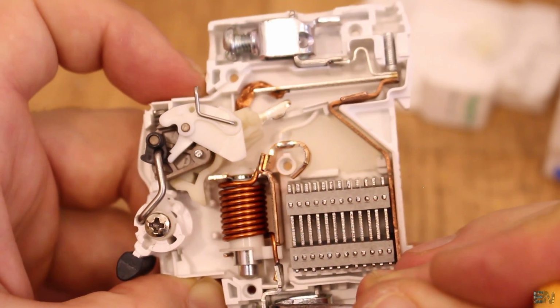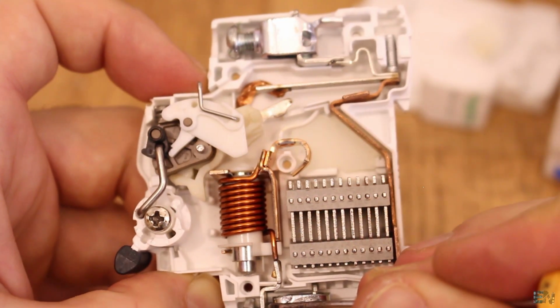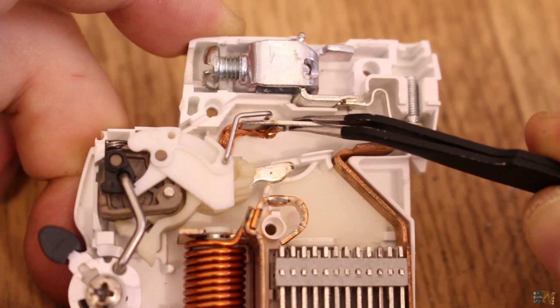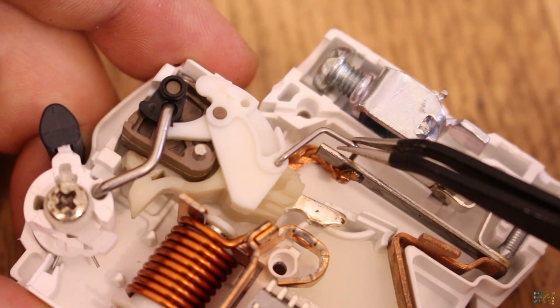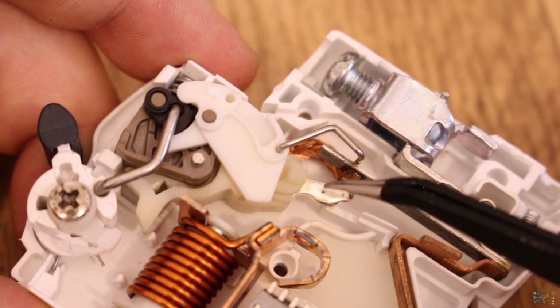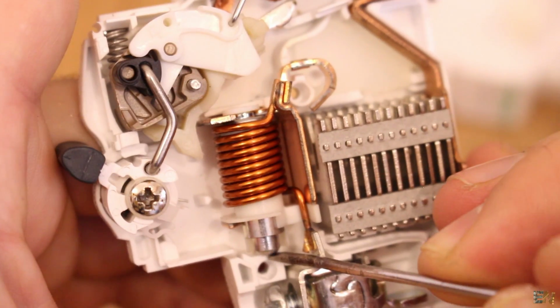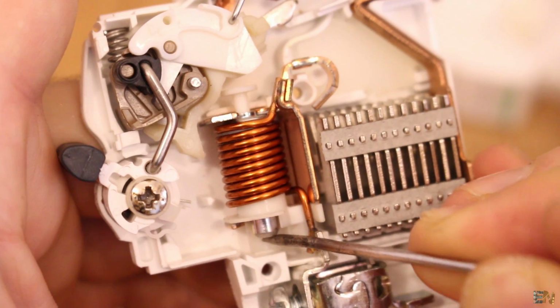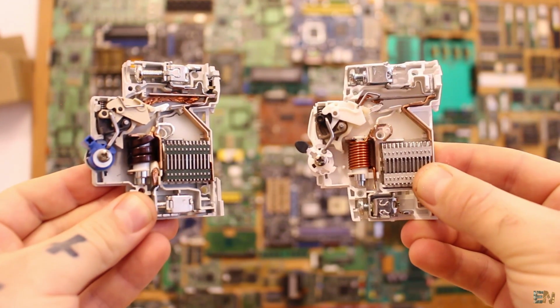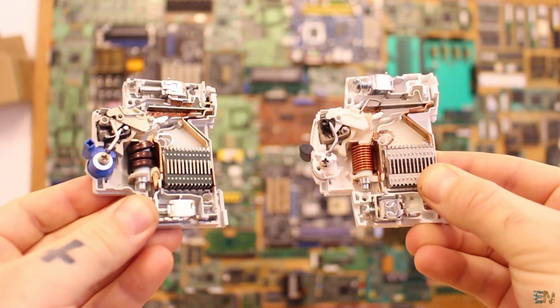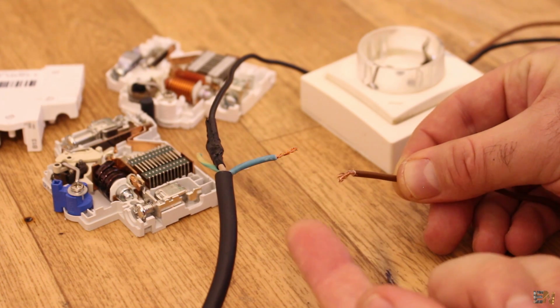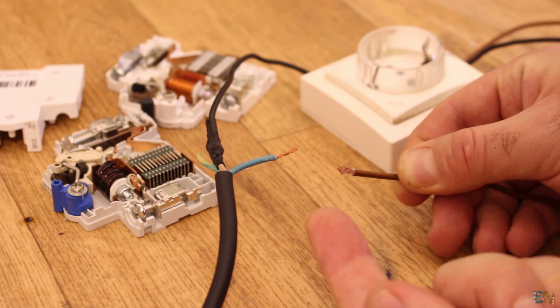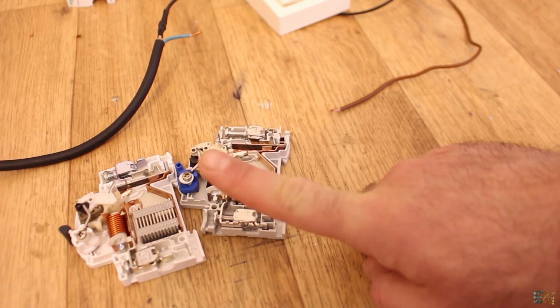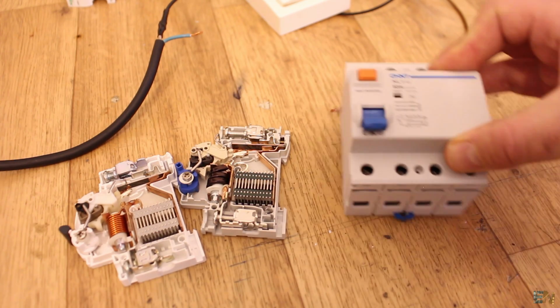The thermal protection changes the metal shape and removes the lever. And the magnetic protection creates a magnetic field and pushes a metal piston. That's why this device is a thermal magnetic breaker, because it has both protections in the same device. Okay guys, but this MCB won't protect us, only the wiring. I mean, if I touch a live wire and shock myself, the MCB won't do anything, because the current is not high enough and we don't have a short circuit either.